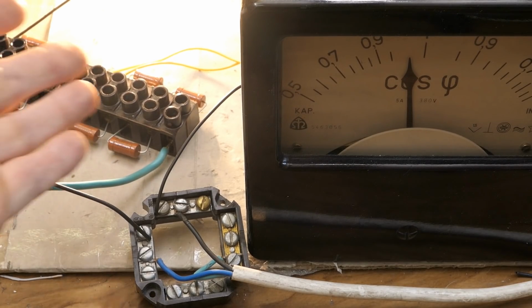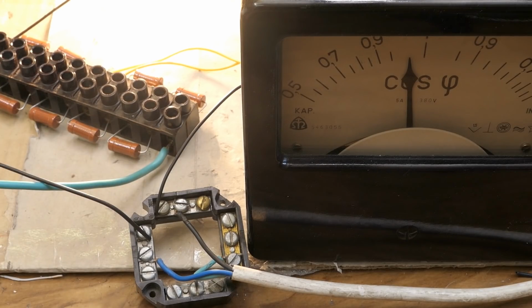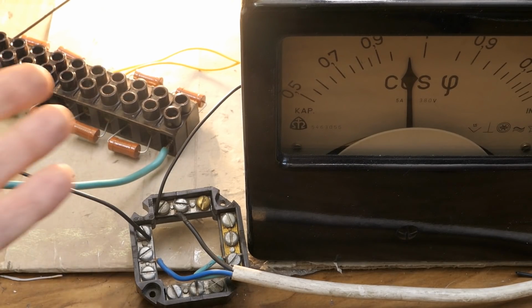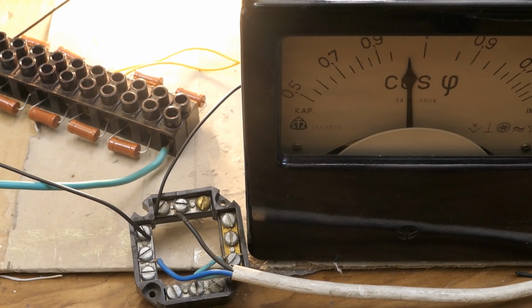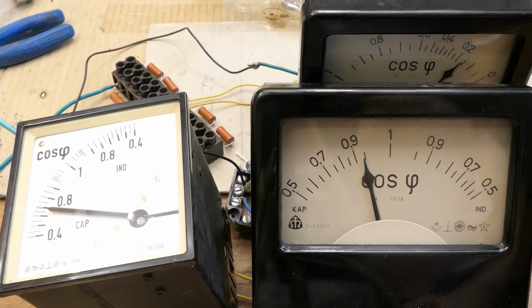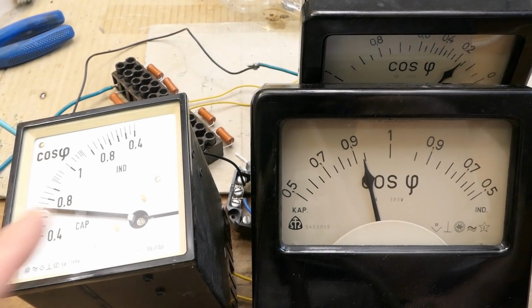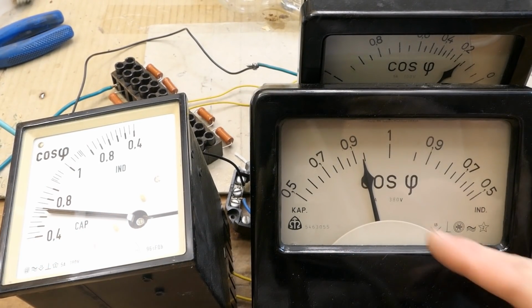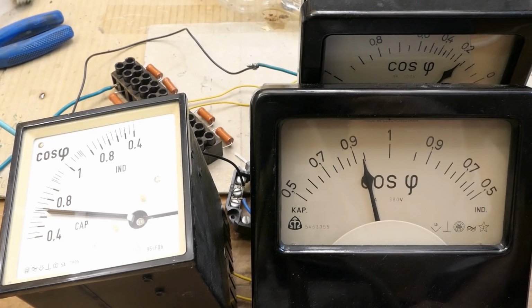Or maybe the current in the voltage coils is just all too low. But I don't want to risk using much more current, not knowing what it originally was meant to be. So that's the power factor meters. This one seems to work well. This one also works. It probably just needs a little adjustment or a little bit more current, or balance the current between the coils a bit better.